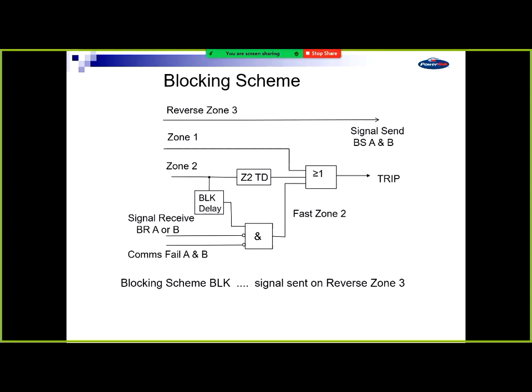We send 2 signals. So the BS stands for a block send, and we send an A and a B, different paths, so different ways to get there, so it's secure and reduces the common mode failure. So down the bottom you see a receive A or B, so it's not one of those, not both of those comms fail. If both of those communication paths fail, we put a permanent block on there, so it can't go fast, can only go slow. So you see the zone 2, with the zone 2 time delay going straight through on the right there, nothing stops a trip after that time delay. That's a settable setting in all distance protection. You do a zone 1, a zone 2 with a time delay, and your zone 2 will always operate after that time delay.